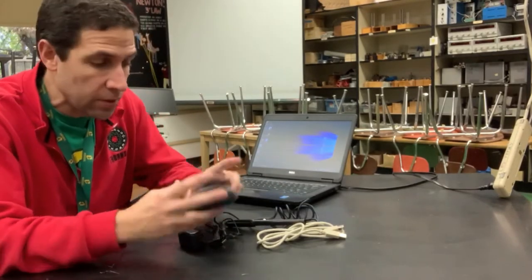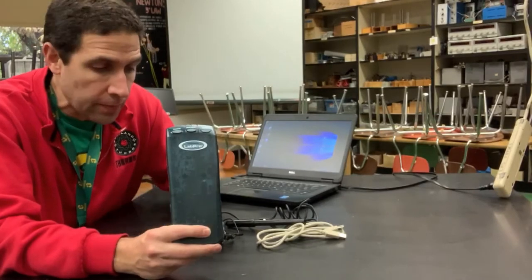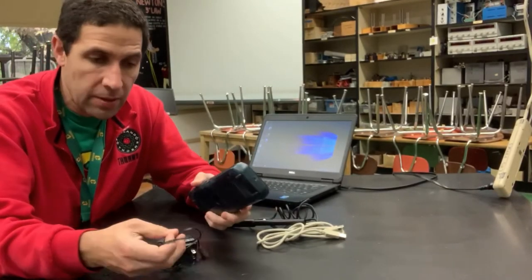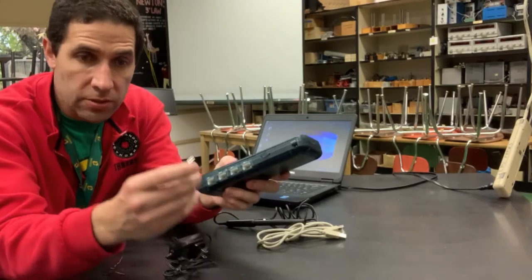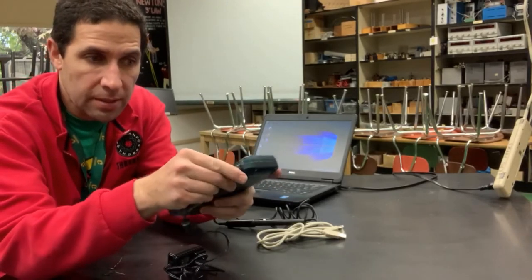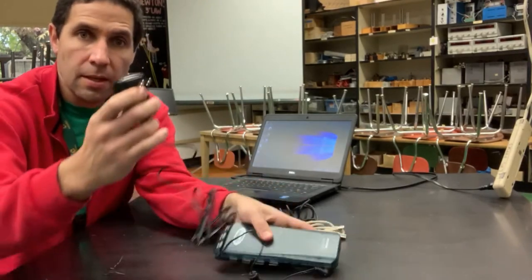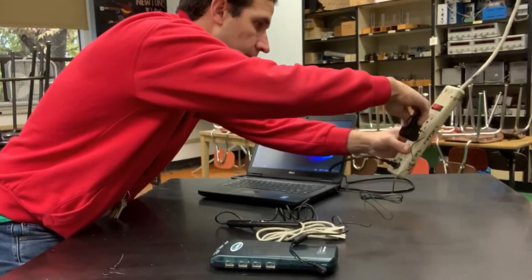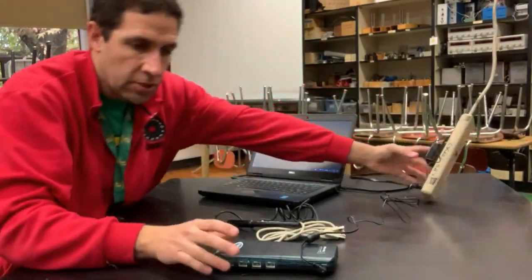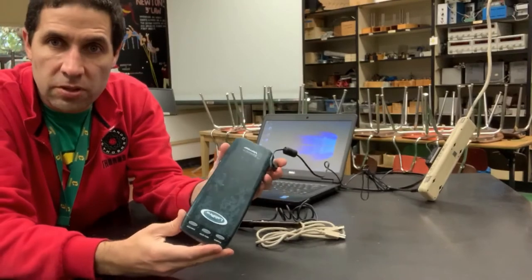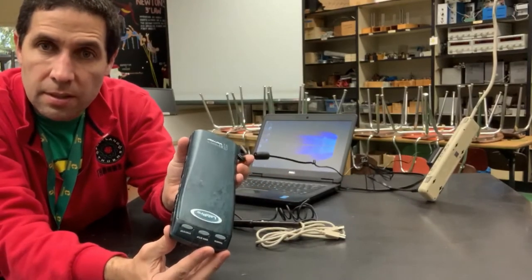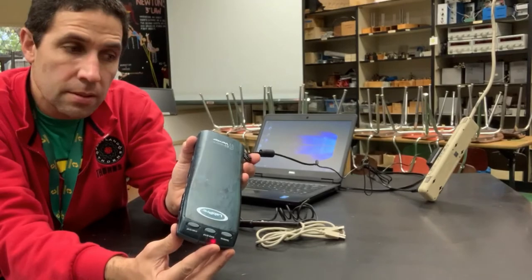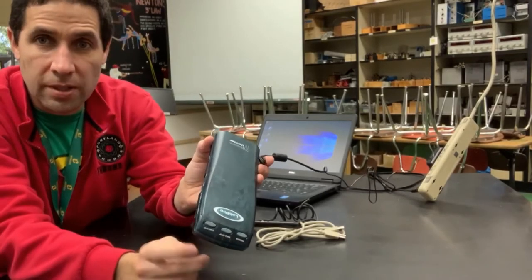First of all, you're going to have to use a LabPro, and so to power up the LabPro you're going to take the power supply and insert one end into this spot right here. I'm going to insert the other end into a power source, and you should listen because within a few seconds you should hear a noise. That's the noise you want to hear. That tells you that the LabPro is powered up.